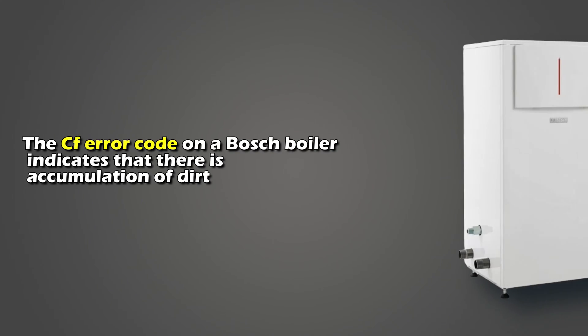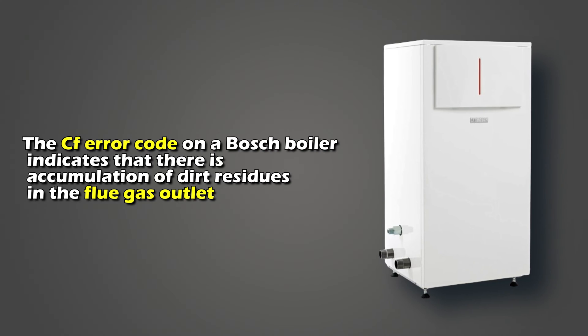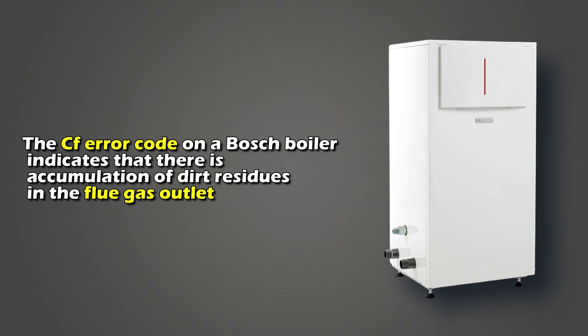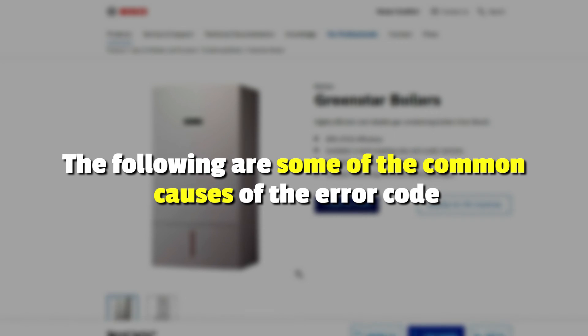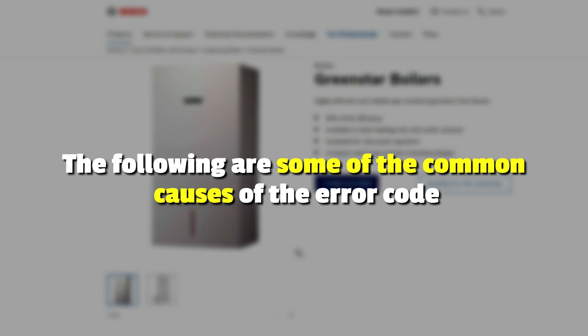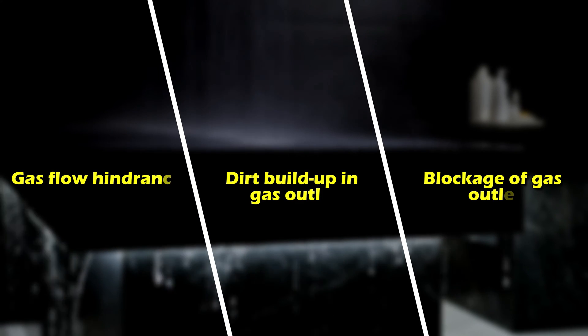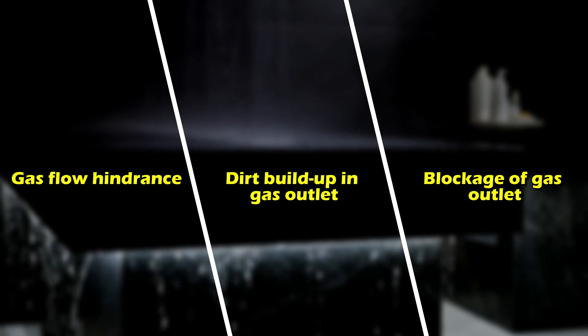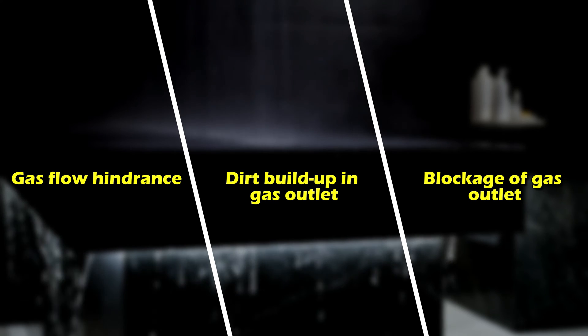The CF error code on a Bosch boiler indicates that there is an accumulation of dirt residue in the flue gas outlet. The following are some of the causes of the CF error: gas flow hindrance, dirt buildup in the gas outlet, or a blockage of the gas outlet.